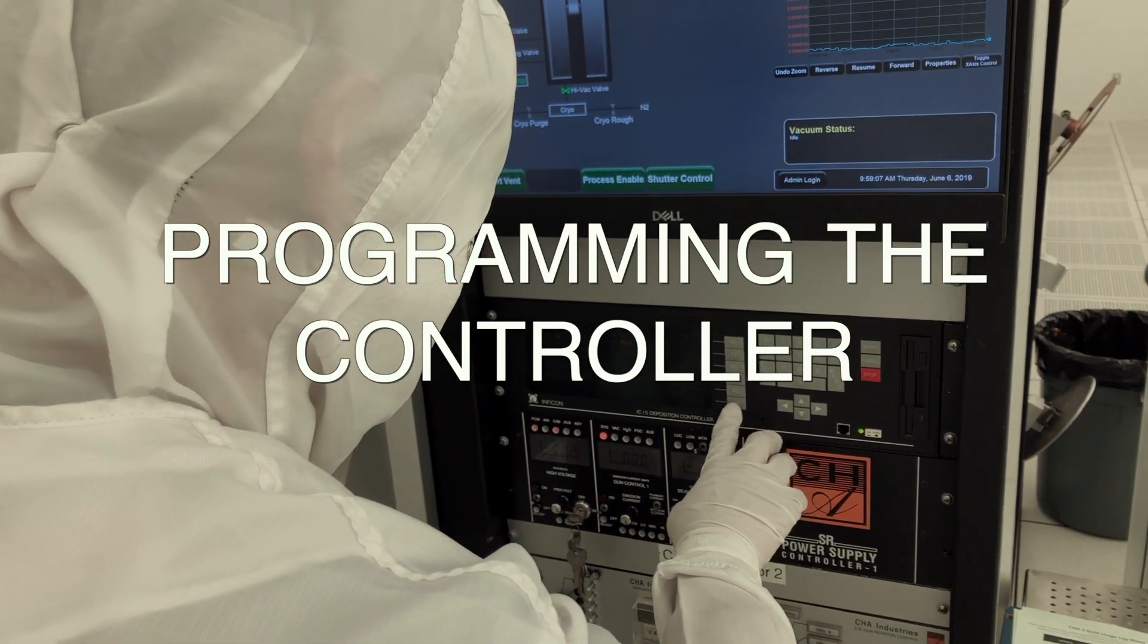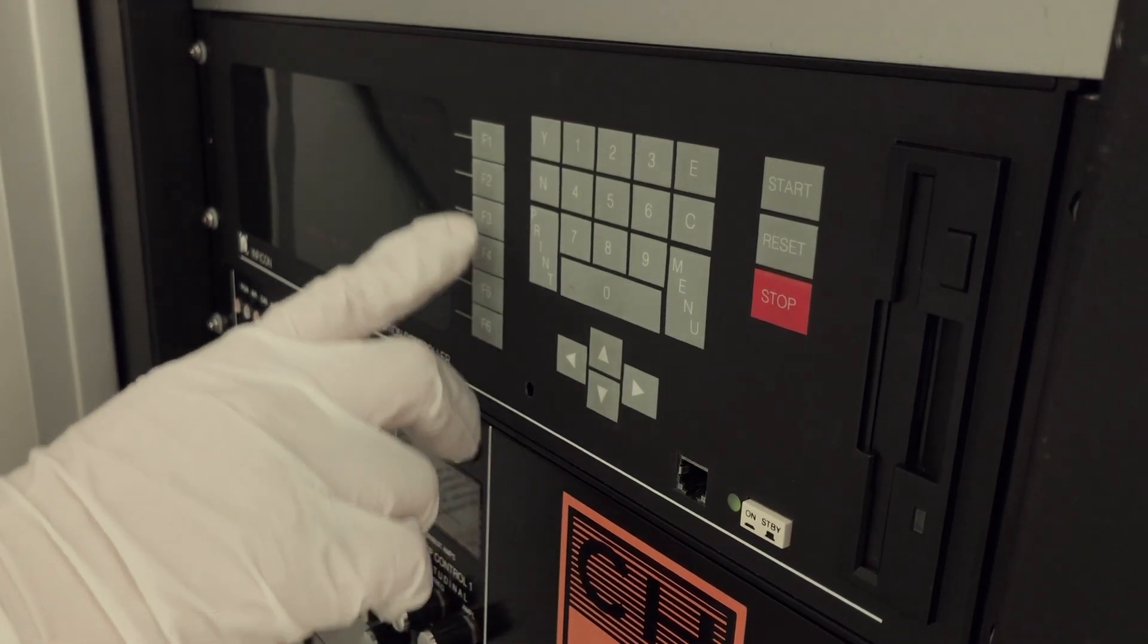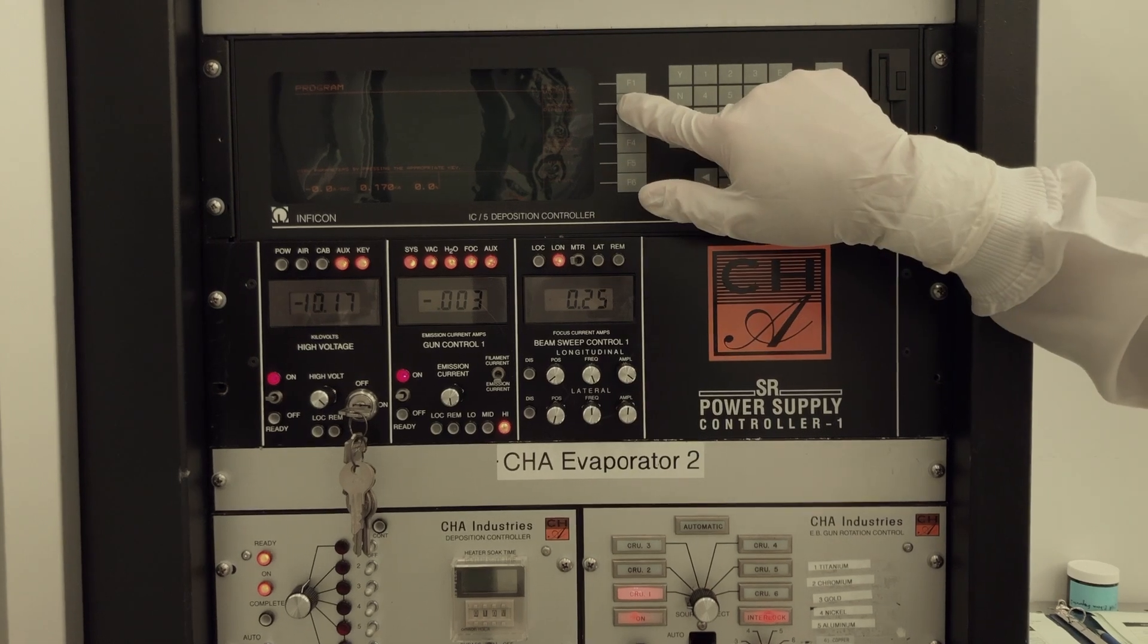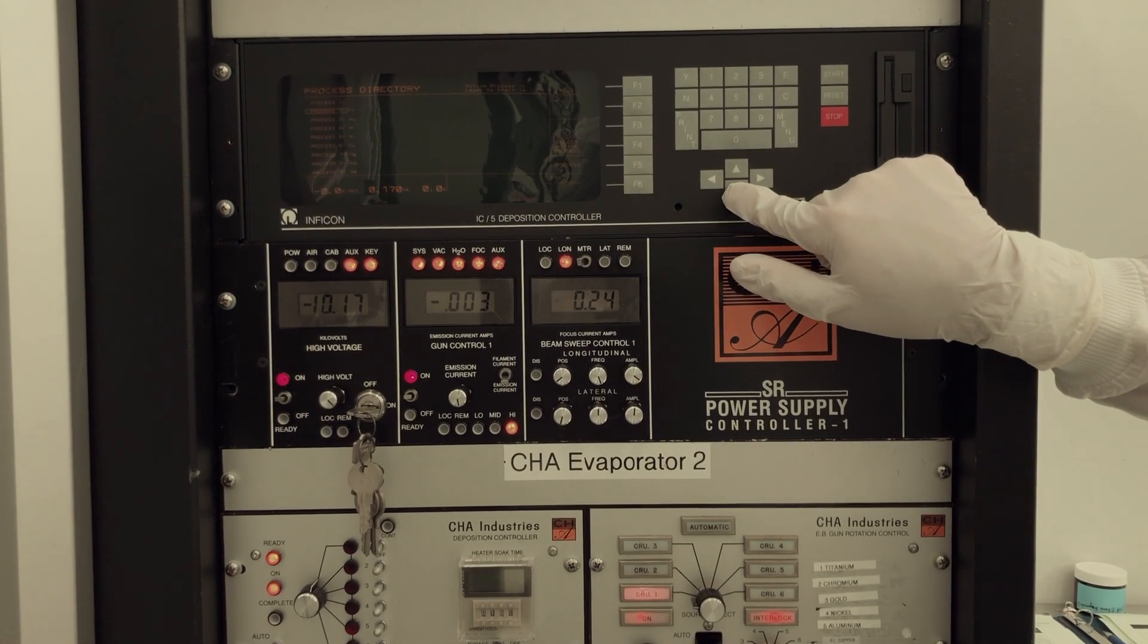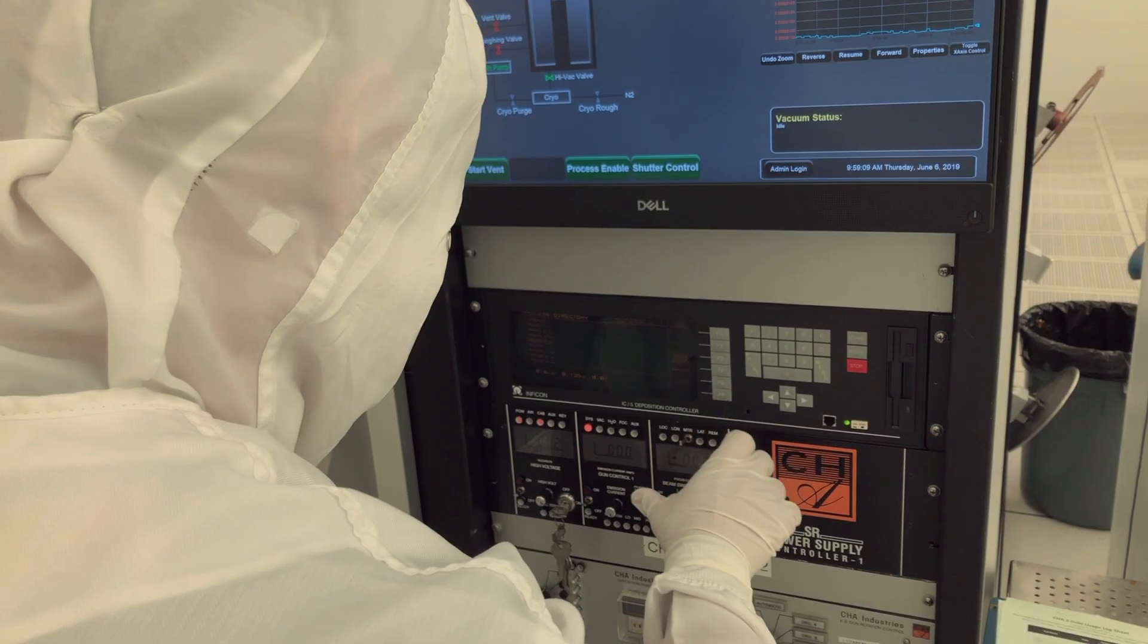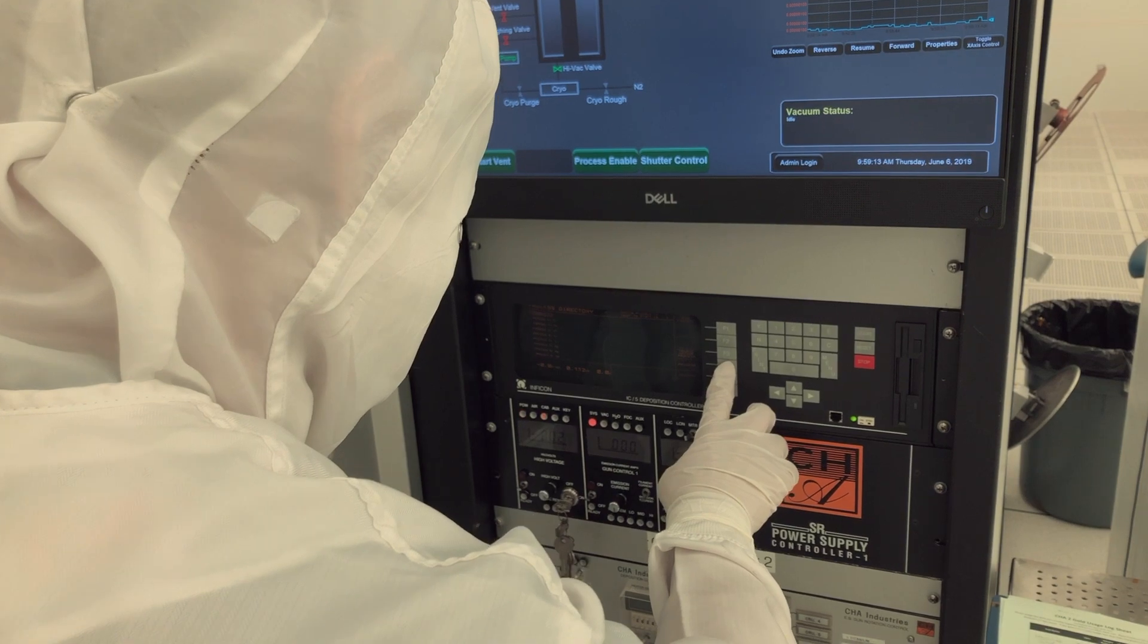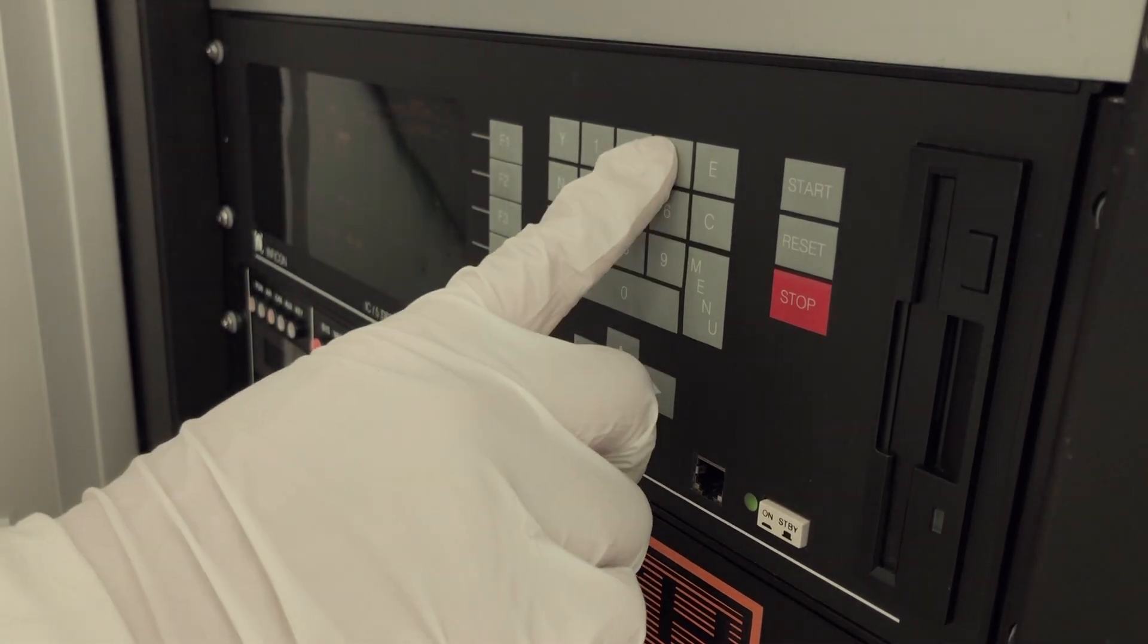To begin programming the deposition controller, press F6 for program on the keypad. Then press F2 for process directory. The controller will display a list of materials. You will need to set up each material that you are going to use during your process run. Use the arrow keys on the keypad to highlight the material you want to set up. Press F5 for process to display the settings for the material.